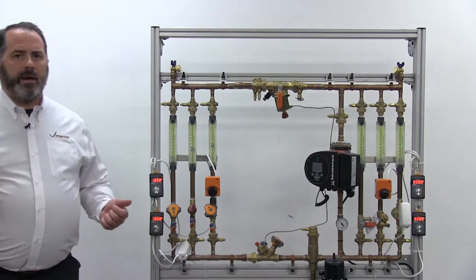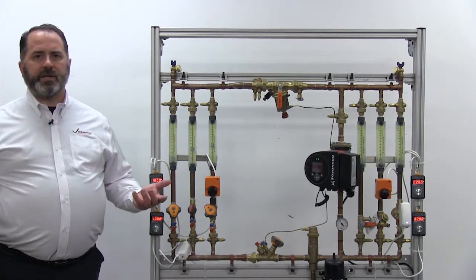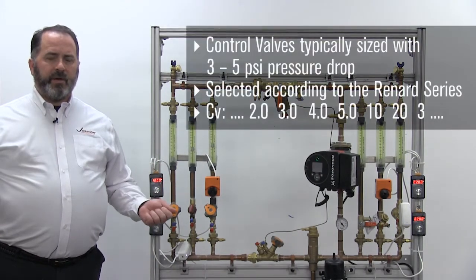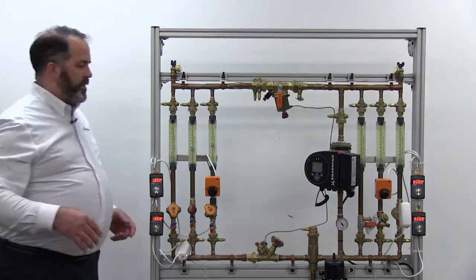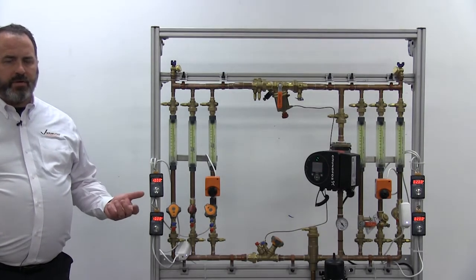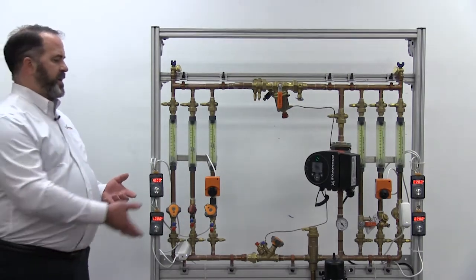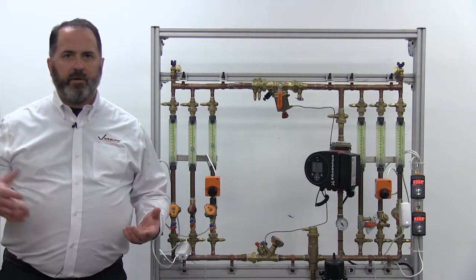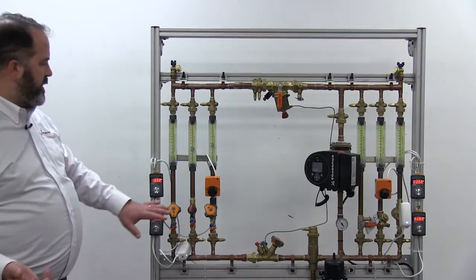CV is selected based off of the selections that the manufacturer will have. Usually there's about five or six per size range of different CVs. But if you look at the available CVs for those, there'll be wide gaps in between each other. Other issue is that most of your controls contractors don't always select the best control valve for the system. A lot of time, they'll take a one CV fits all for a system or they don't really put the time into calculating flow or calculating the actual CV requirement for that part of the system.